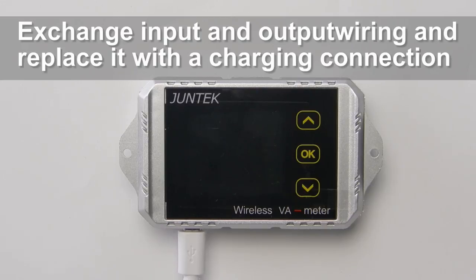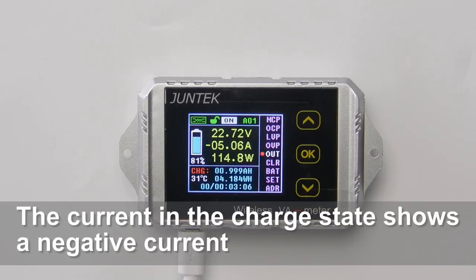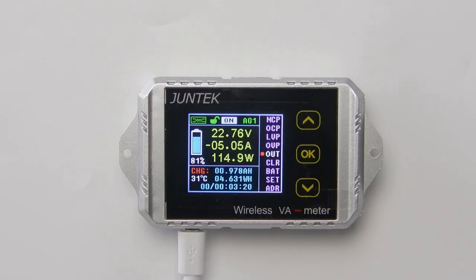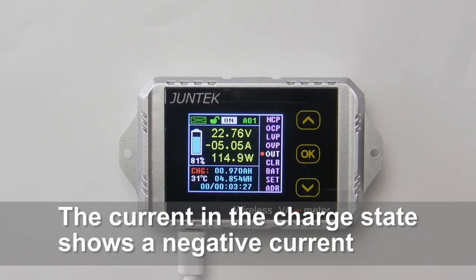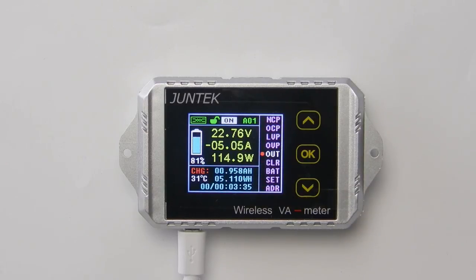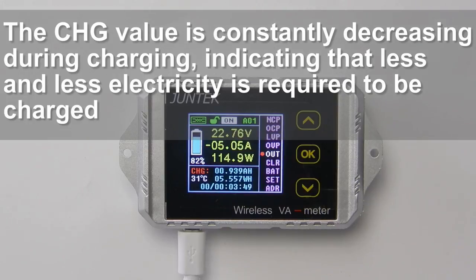Exchange the input and output wiring and replace it with a charging connection. The current in the charge state shows a negative current. The CHG value is constantly decreasing during charging, indicating that less and less electricity is required to be charged.